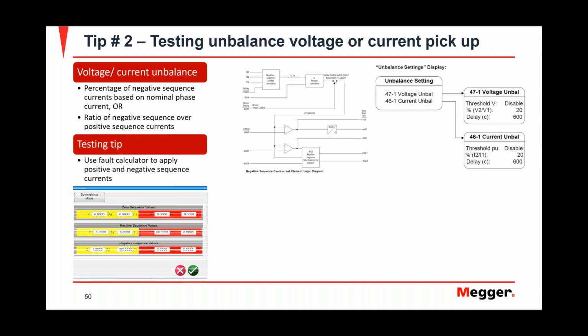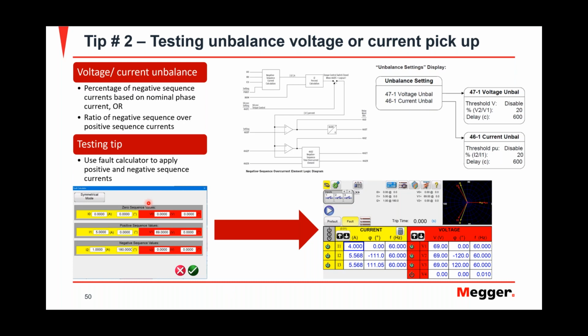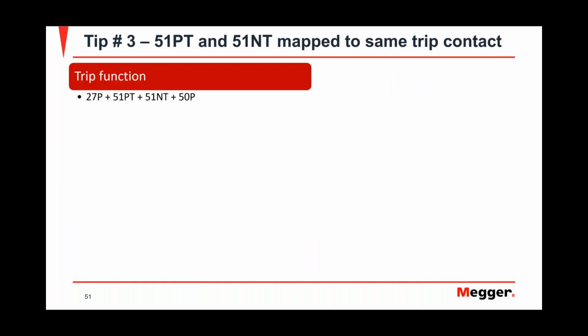current. The easiest way to test these is to go into the software of your relay and look for a fault calculator. In that fault calculator, you're able to set positive sequence current and negative sequence current, the values that you get from the settings. And this tool will automatically translate them into your phase values. That way you can test it much more easily. You don't even have to understand sequence components. As long as you understand the basic theory, you can apply this tool, which is in most relay testing software, and it will make your testing a lot easier. When I learned that, it was an eye-opener using that fault calculator.